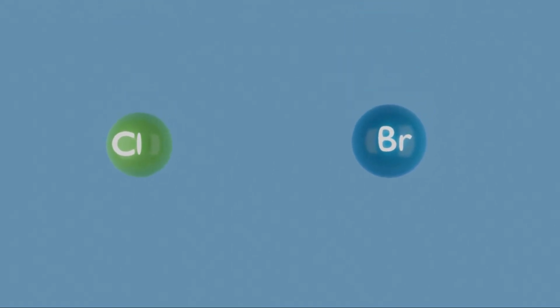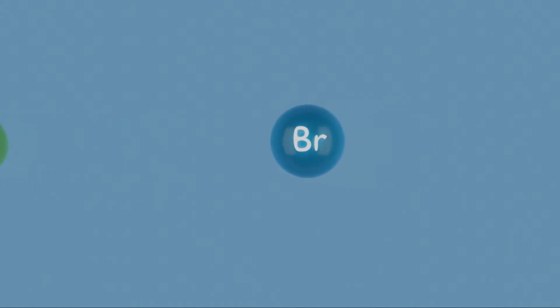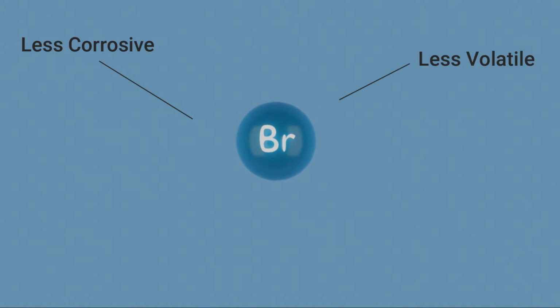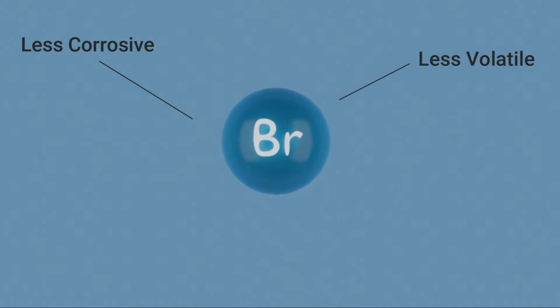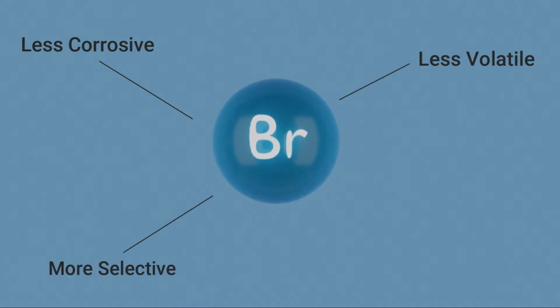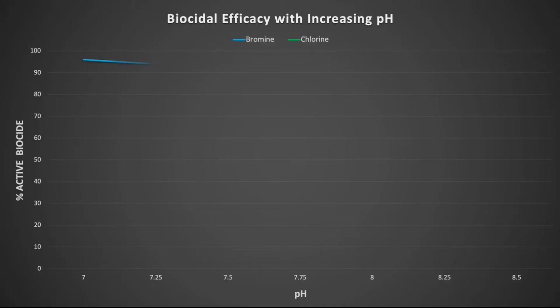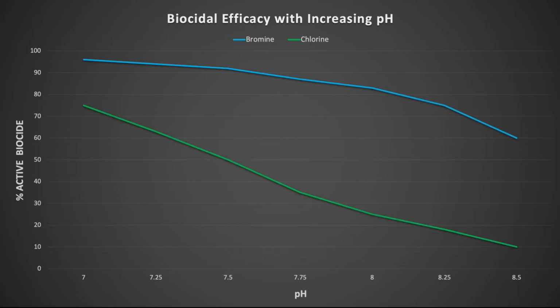There are, however, a number of reasons why bromine is often preferred to chlorine. It is less corrosive, it is less volatile, it is less affected by contaminants such as ammonia, and most importantly, it is much more effective in the more alkaline pH conditions that are present in most cooling systems, which means that it provides effective control without the need to dose acid to lower the pH.